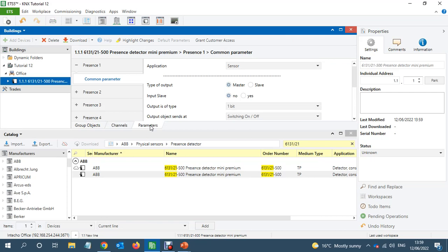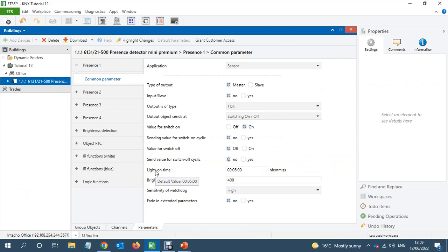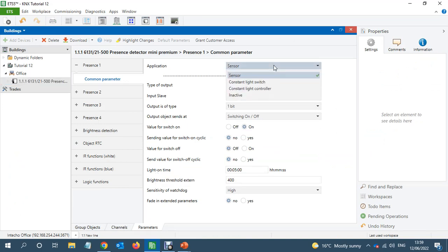So what we need here is we're going to use this sensor as a constant light controller. What we want is to achieve 500 lux all the time if there is a movement in the office area.